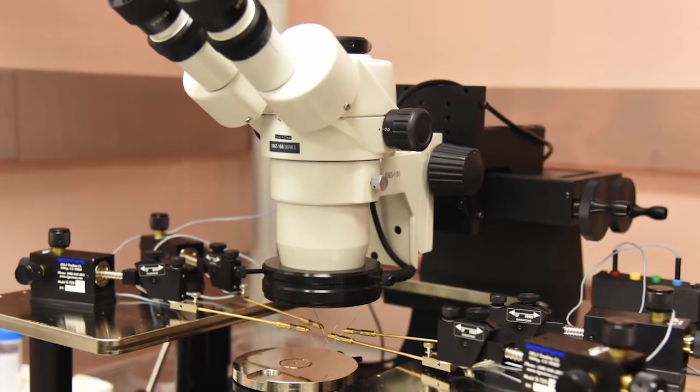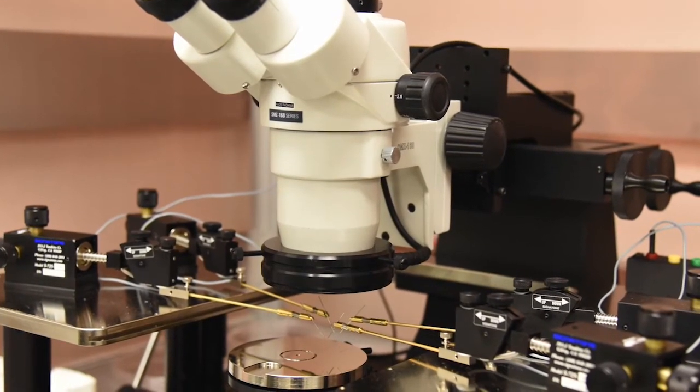For the nanoneedle, we've figured out exactly how to prepare the blood and get reproducible results. We've also found that we can keep blood at room temperature for quite a while and still get a good signal, which is incredibly helpful so we don't have to process it instantly. This instrument here is a new probe station that can now do two chips simultaneously. That's quite useful for the science — it means we can run a healthy control alongside a patient, or run a patient sample with and without a particular drug. Those are the studies that are going to start next.